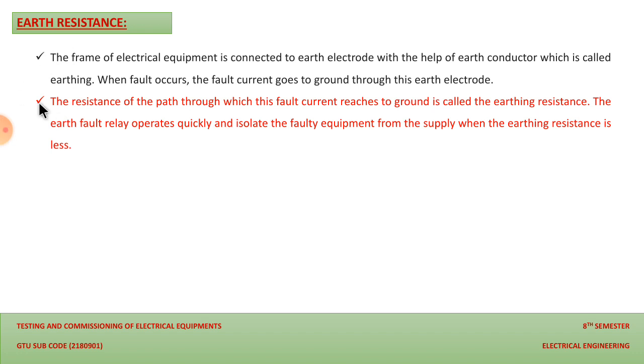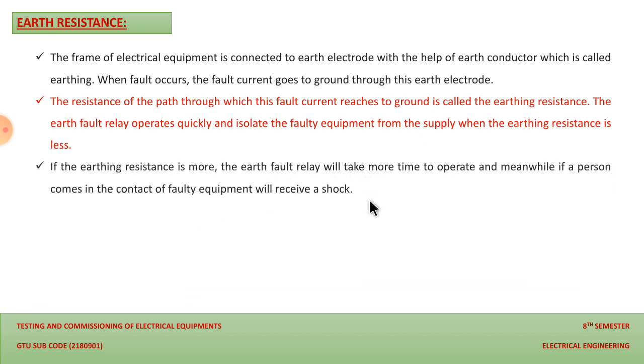And if a person comes into contact with faulty electrical equipment, there is a high discharge because of the fault. So earthing resistance is the resistance of the path taken by the charges which are discharging through a medium. So yes, we should keep this resistance as low as possible, so that we can operate the earth fault relay, as well as protect the equipment and human beings whenever such a fault occurs.